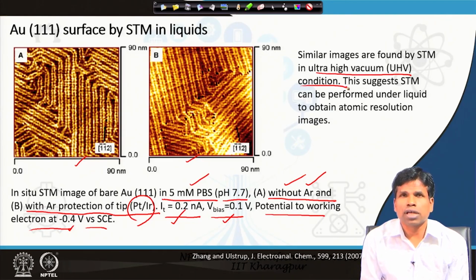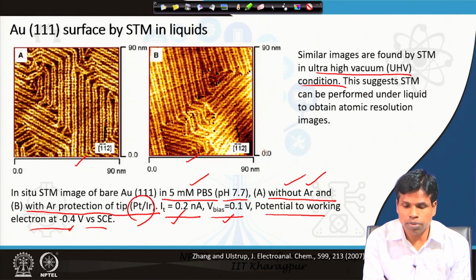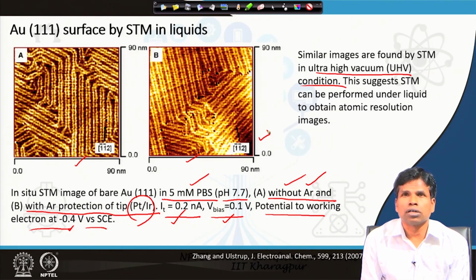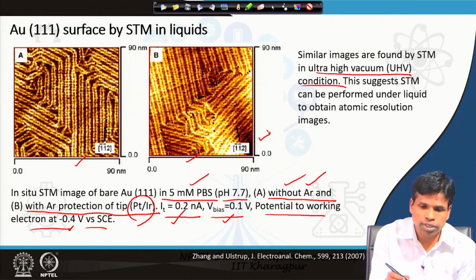In this type of STM study, we exclusively measure the surface properties at the atomic scale. Therefore, cleanness of the surface is very important, but in this particular study, as we see, it is done under liquid. It is not possible to do measurements of liquid in ultra high vacuum, but the information obtained with the gold sample in the liquid medium is almost similar to that taken in the ultra high vacuum condition, providing atomic resolution.